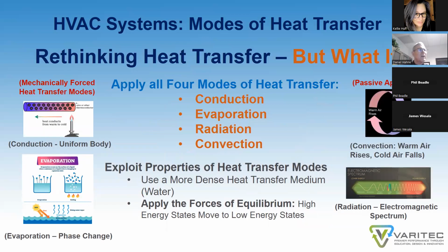So instead of a conventional system, what if we rethink the modes of heat transfer that we have historically and traditionally applied? What if we exploit all 4 modes of heat transfer? We would still use the mechanically forced heat transfer modes of conduction and evaporation, either through air handler cooling coils or chiller vapor compression cycles. But what if we take a passive approach to heat transfer?